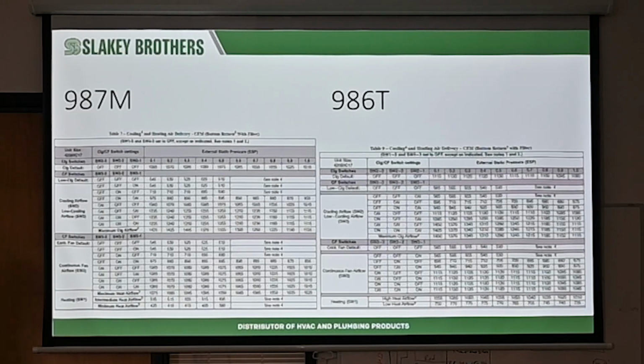Okay? So again, just make sure you see how the numbers are pretty close. So whatever you're doing, like this is a 3.5 ton capable furnace. If you put a 2-ton air conditioner, you can still do it. Make sure you're adjusting your dip switches so that you're getting your 800 CFM, so that this furnace will work with a 2-ton unit, for instance. If you put in a Connex controller, automatic. It will automatically do it for you. Now for a 2-ton unit, maybe a 5-ton furnace may not work.